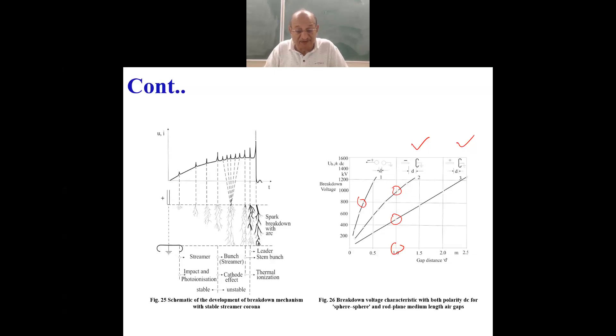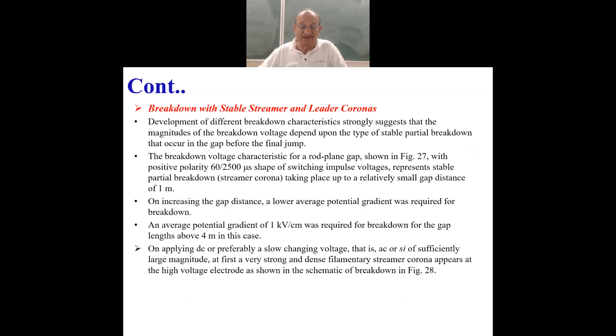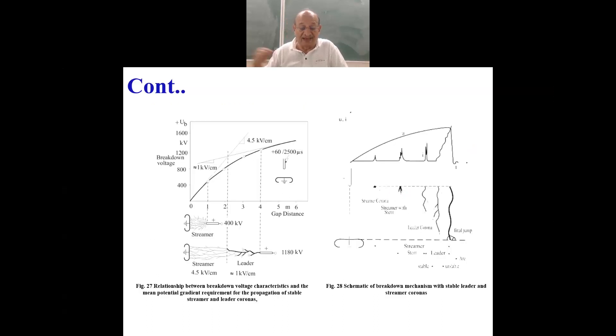We will learn further that there is also a very predominant effect when you measure the breakdown strength under any field condition with different kinds of voltages. This has been measured with positive and negative polarity DC. If you measure with AC it will be slightly different. If you measure with lightning impulse it will be different. If you measure with switching impulse it will be different. So you cannot say that the breakdown strength of air has a certain fixed value.